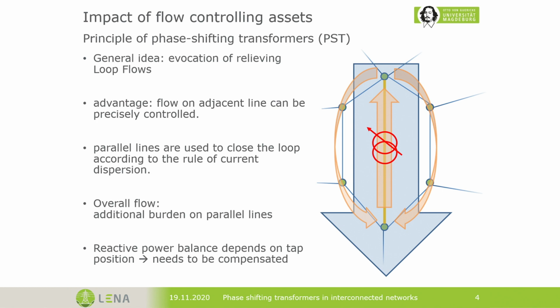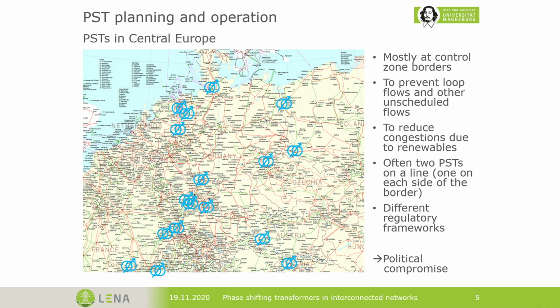The circle has to close somehow, and this is done using the parallel lines to this line that I want to remedy. So this means using this PST here means that the adjacent lines, so the parallel lines, will be burdened a little bit more. So this is very important. We have to keep this in consideration. So the flow is shifted from our main line that we want to remedy to parallel lines, which means that this PST does not affect only the specific line, but all lines in the system. And if you want to place several PSTs, this is very important, so the PSTs don't start to fight against each other. One solution to these loop flows are, for example, these PSTs.